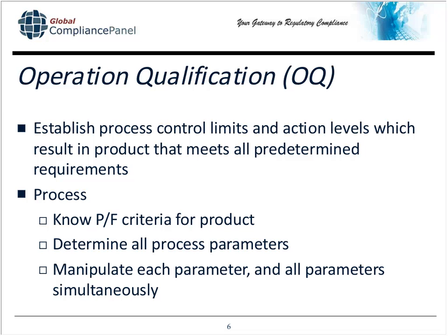The process for the OQ is obviously to know the pass-fail criteria for the product or process. We'll talk a little more about the sealing machine, but on the low end, the pass-fail criteria for a sealed pouch is that it's not sealed. You get below a certain temperature, for example, and that pouch is not sealed. The high end of the pass-fail criteria is that the pouch can't be burnt or have an otherwise less than perfect physical appearance, a cosmetic appearance.